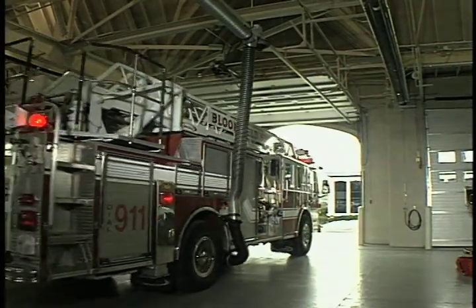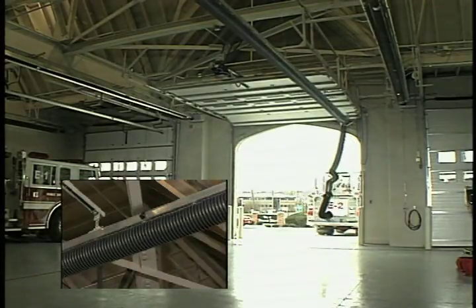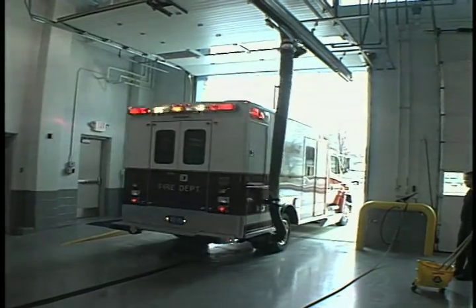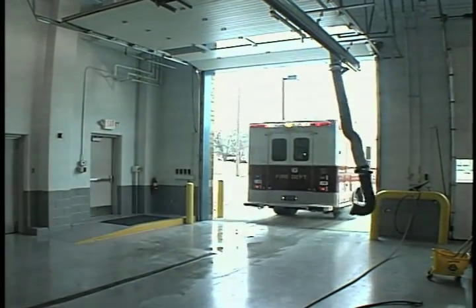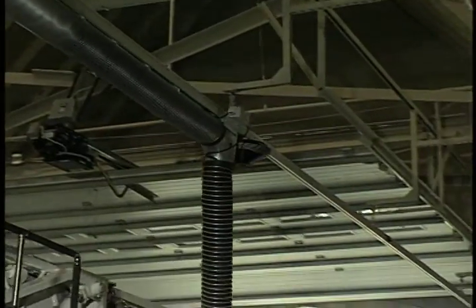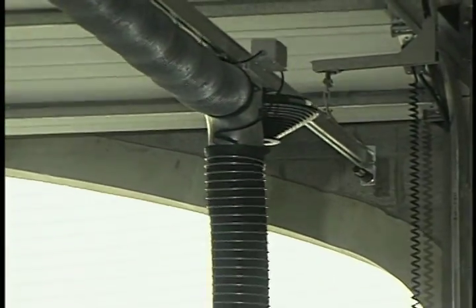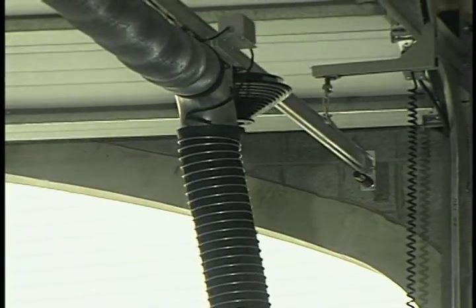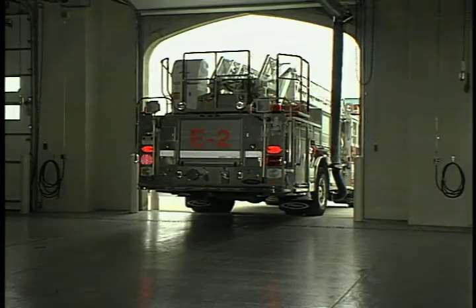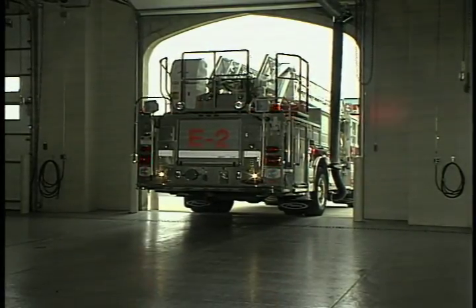Once again, as the tailpipe passes the exit door, the electromagnet is automatically de-energized when passing a disconnection point, allowing the nozzle and hose to smoothly separate from the vehicle. The balancer keeps the vertical hose off the floor at all times, so no premature scuffing or wear occurs. Upon return, the Magna Track is easy, simple, and as you can plainly see, safe to use.